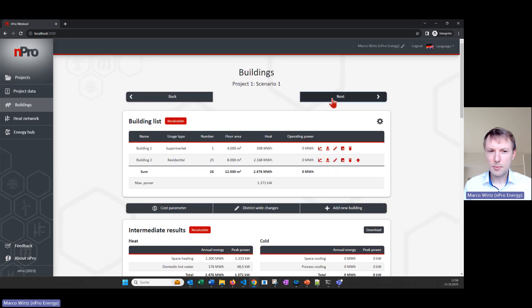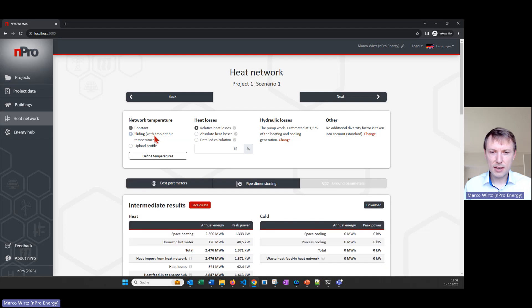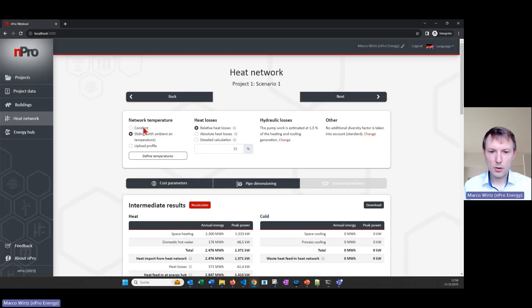I want to go to the next page — that's the heat network page with all the settings about the network itself. Here we can define the supply temperature of the heat network. We can also define a sliding temperature curve, so in winter it would be higher than in summer. If we have a very special configuration we can also upload our own profile.